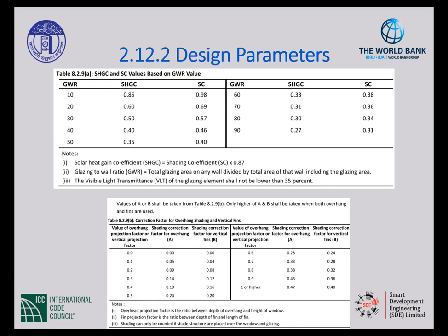What are those design parameters? So, we say we got to design the system for where we're building the building and how we're building the building. So, of course, we're going to have to take into consideration the design. What are the outdoor temperatures for where we're building this building? What are the inside temperatures? This code says you have to use an indoor design temperature of not less than 24 degrees Celsius for cooling, unless something else pops up. But so you have outdoor design temperatures, and there's a bunch of tables that show you how to figure out that value. You have indoor design temperatures, then you have relative humidity that you have to figure out. So there are some tables in there to find that range of relative humidity. And so those are some things that go in there.